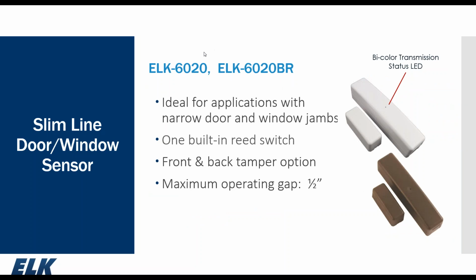All of the other sensors have a built-in bicolor status LED built into the sensor. Maybe a little hard to see, but it's in the center of our 6020 here. When I remove the magnet from the sensor, if this LED lights up green, the communication was acknowledged. The transceiver got the message, turned around, and sent a signal back to let the sensor know it was acknowledged.